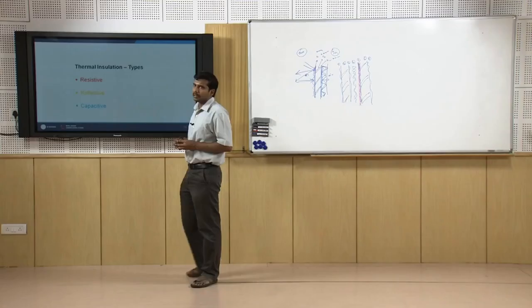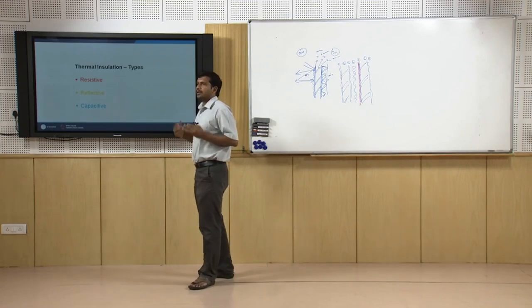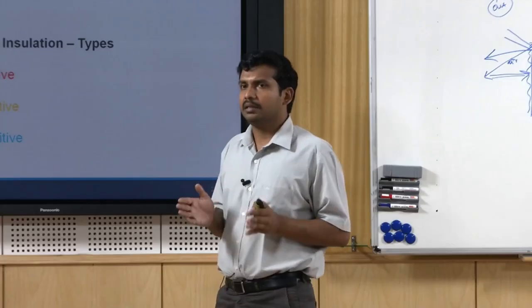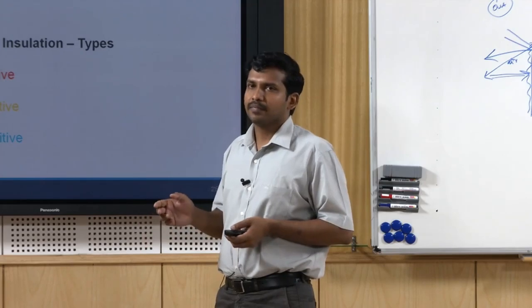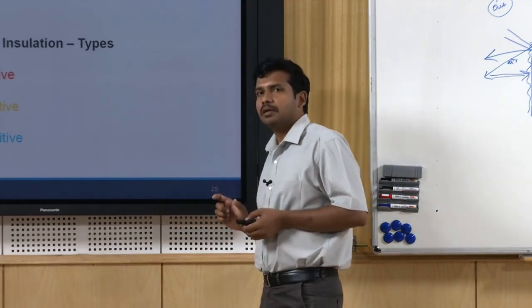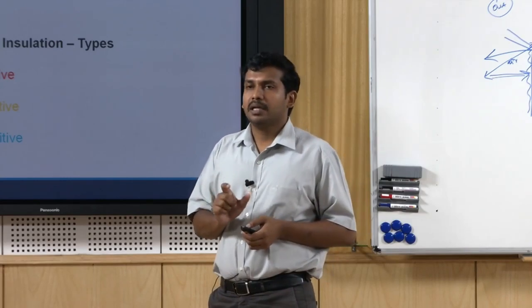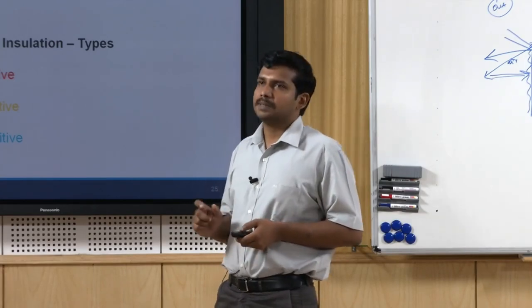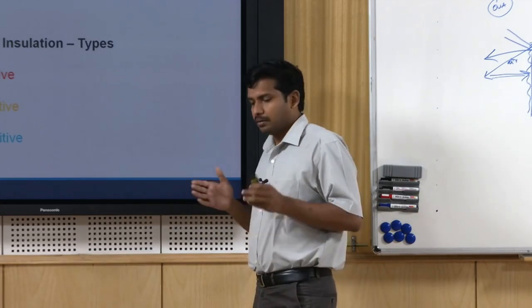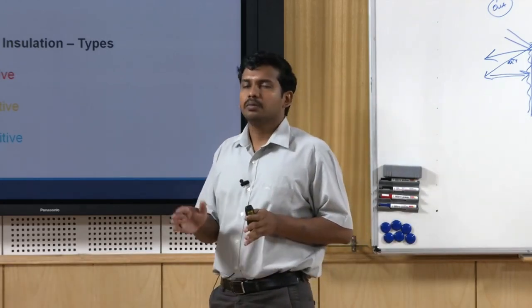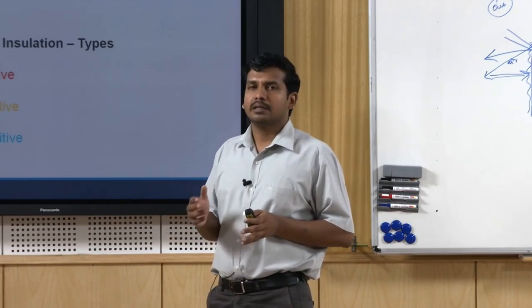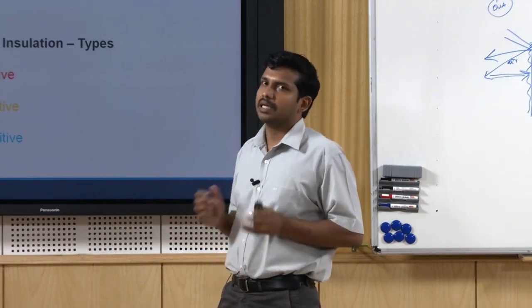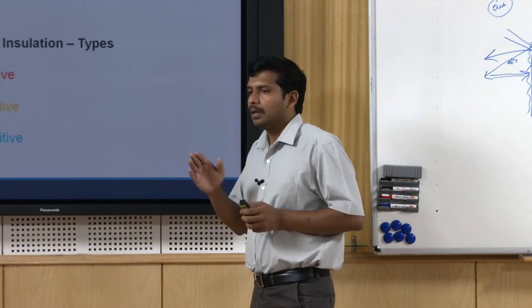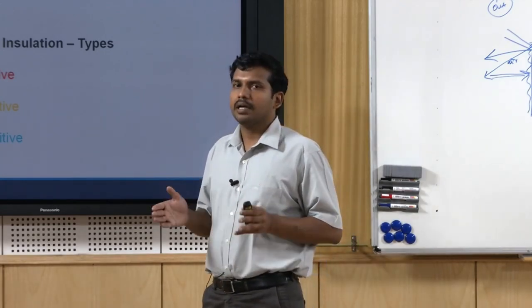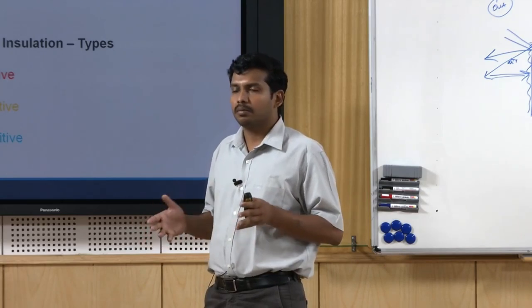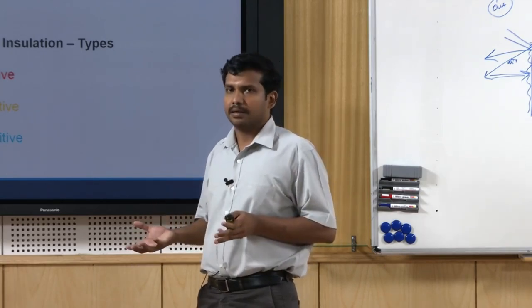But capacitive insulation, say when you use a material like concrete. Typically, people look at concrete as not a very useful material because they think the U value of concrete is high. Imagine a concrete wall of 200 mm or 230 mm thickness. Brick 230 mm has a U value of 2.1 watts per meter square Kelvin, whereas a similar thickness 230 mm concrete wall would have a U value of around 3.5 or 3.6 watts per meter square Kelvin. So, naturally, if you do a conductive heat transfer calculation, the concrete wall will give you more heat load or cooling load because it is transmitting a lot of heat inside.